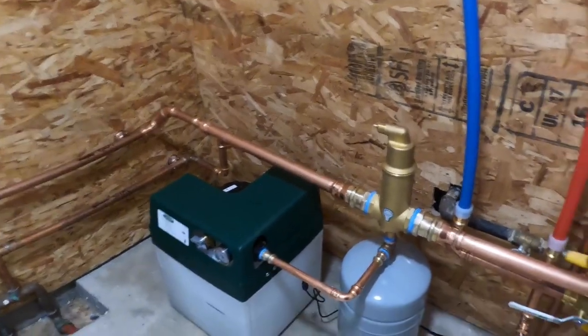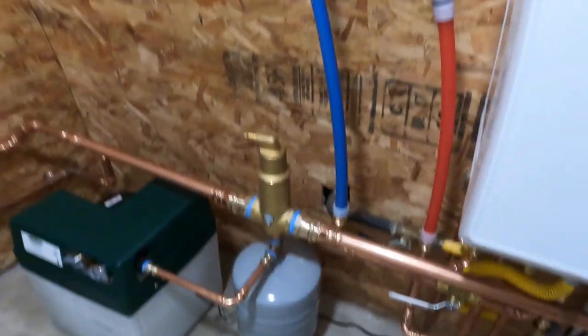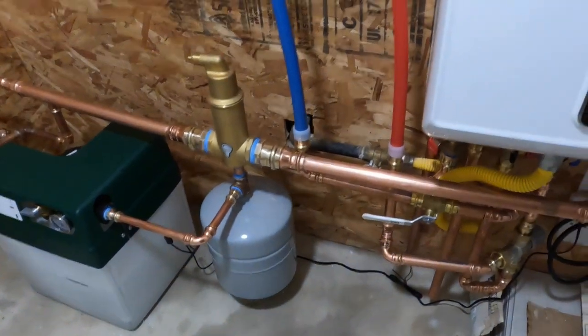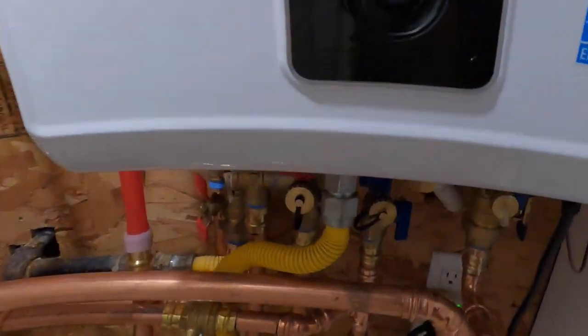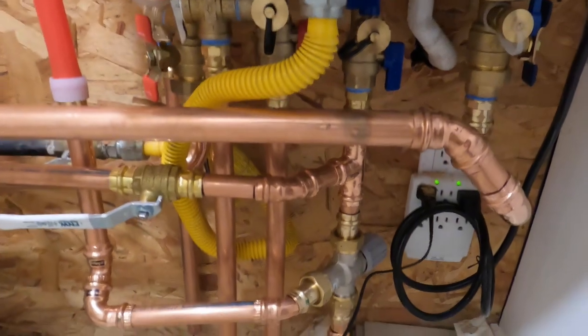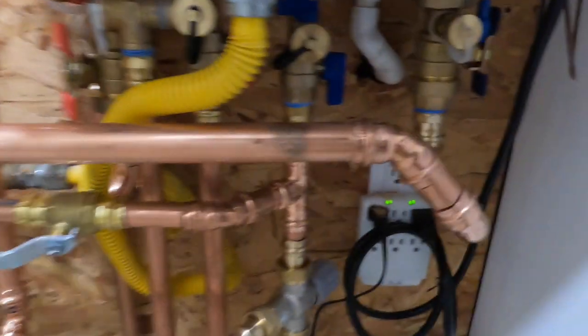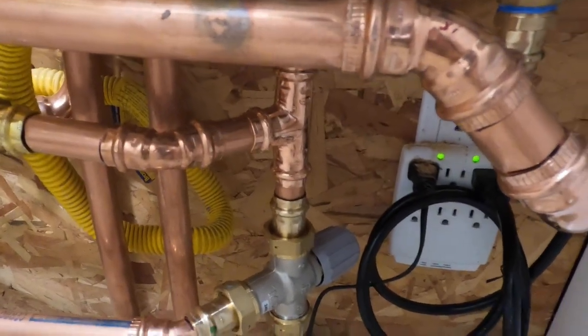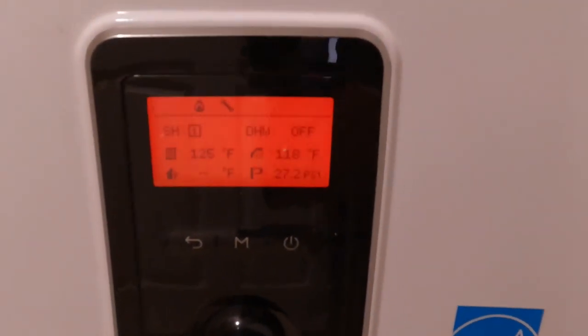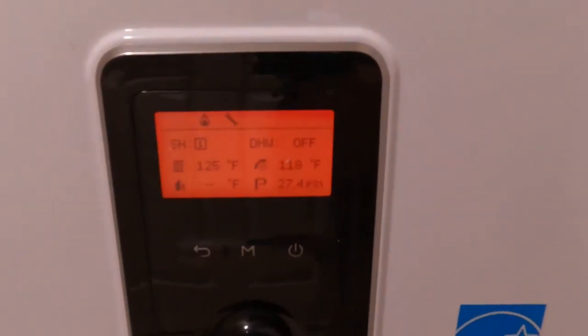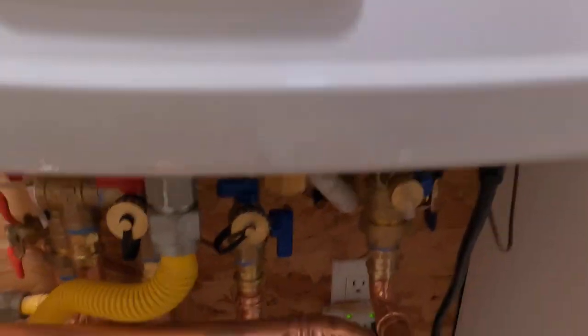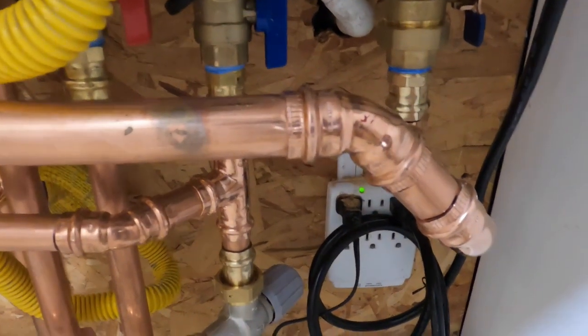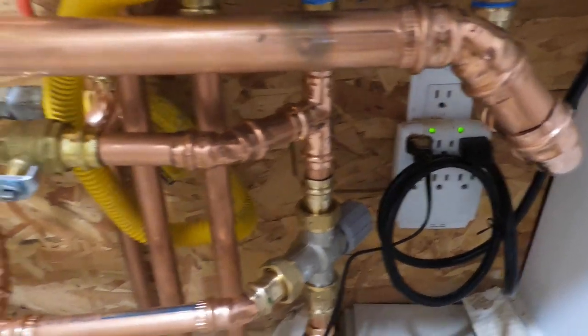There's the Pressure Pal feeder tank. Air separator, expansion tank. All the under boiler piping. Domestic relief valve, heating side relief valve. Domestic mixing valve. We have the boiler set to maintain 140 output on the domestic water coming out of the boiler. That hits the mixing valve and we're mixing it down to 120.